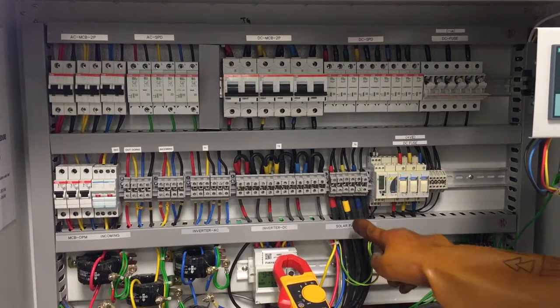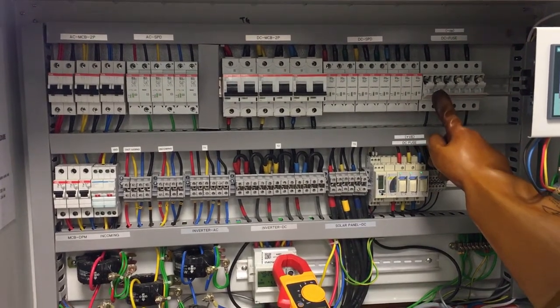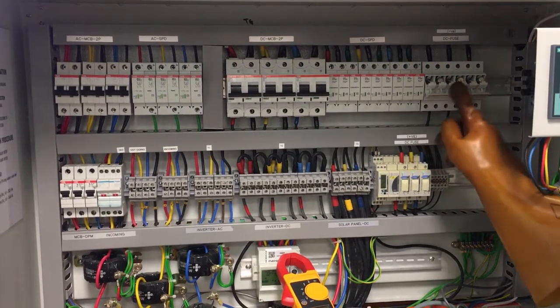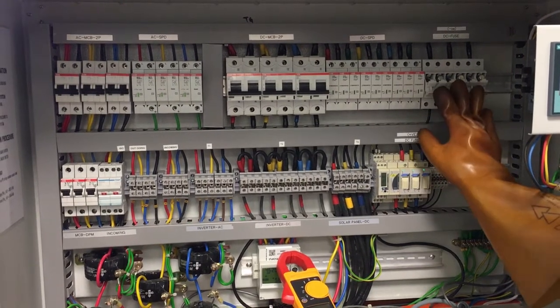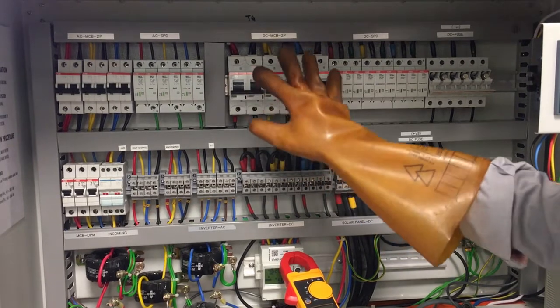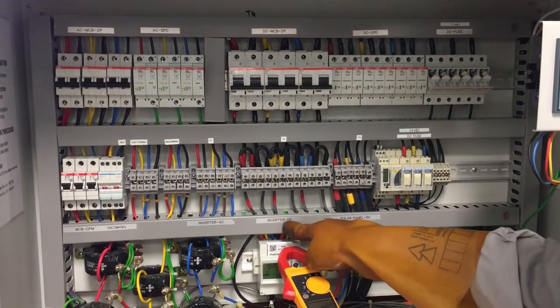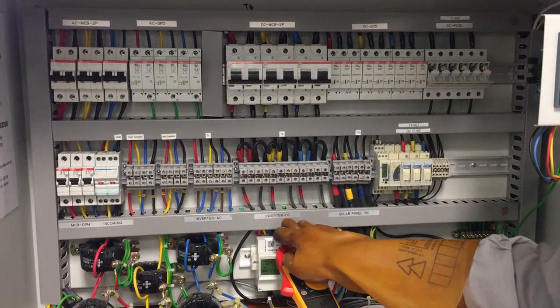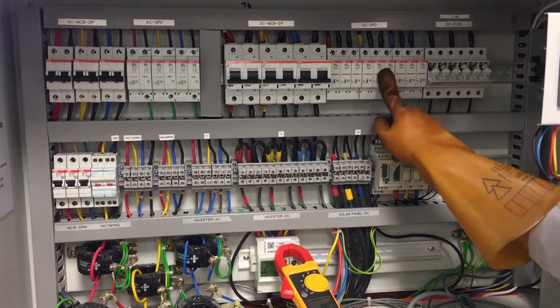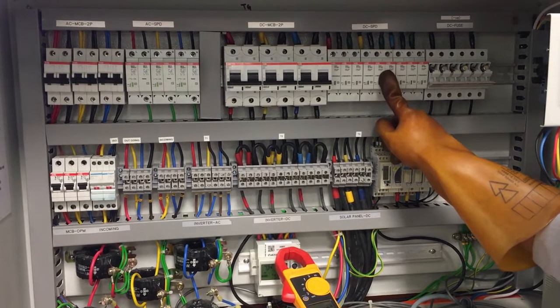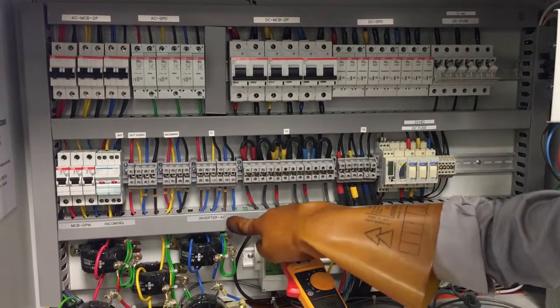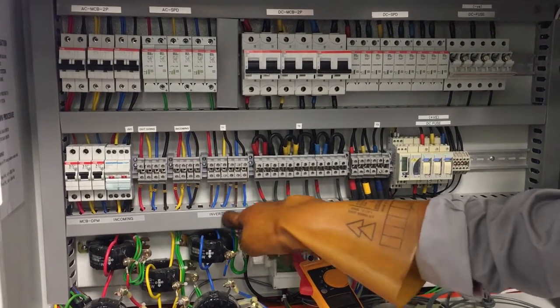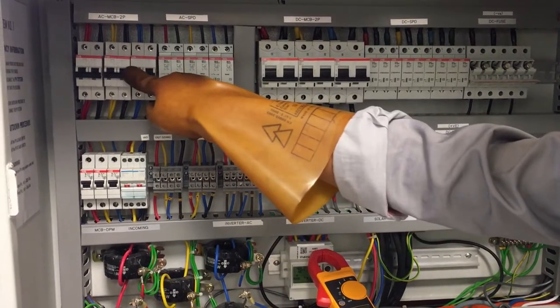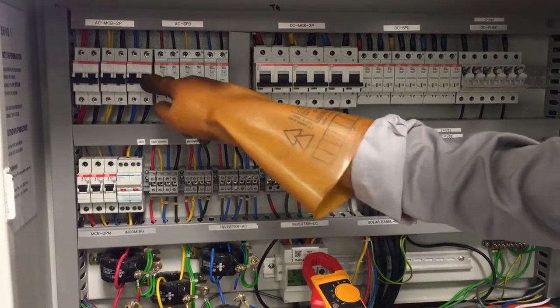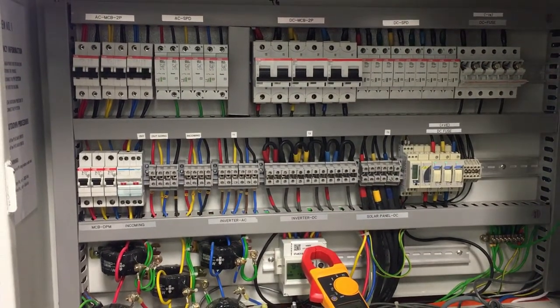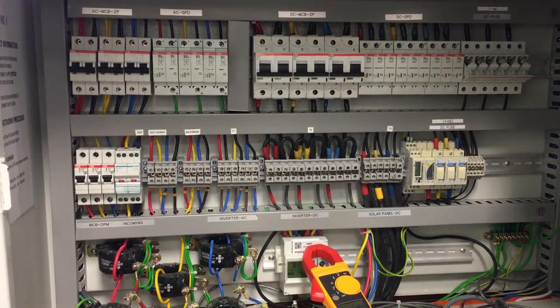From the solar panel DC, the wiring goes to the DC fuse. Here we have 3 inverters, so we have 3 fuses, 3 separate systems. From the fuse, it goes to the DC MCB. From the DC MCB, it goes to the inverter. So here we have the inverter DC. The wiring goes to the input of the inverter, in parallel with the surge protective device, DC SPD. Then coming out of the inverter, we have the AC side, which goes to the AC MCB in parallel with the AC SPD, and then it is connected to the main switch outside of this box, and then connected to the grid. So this is the configuration.